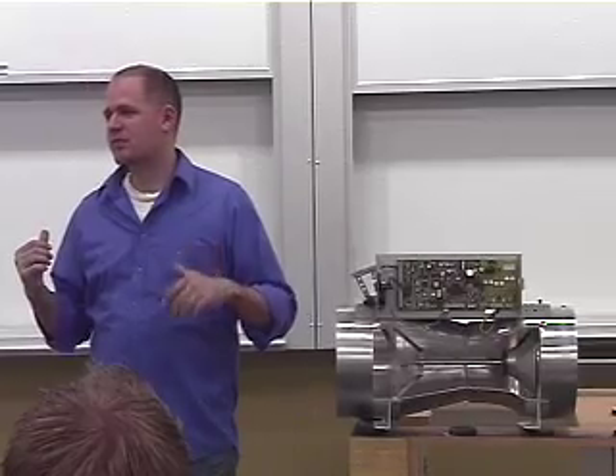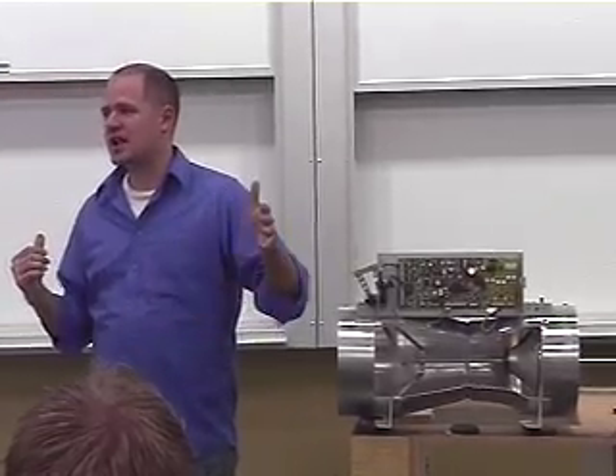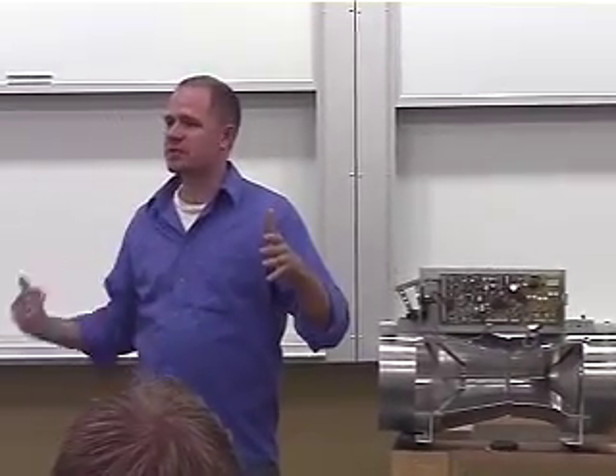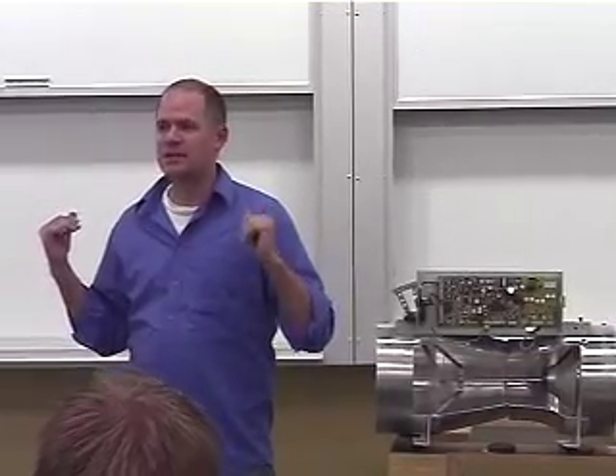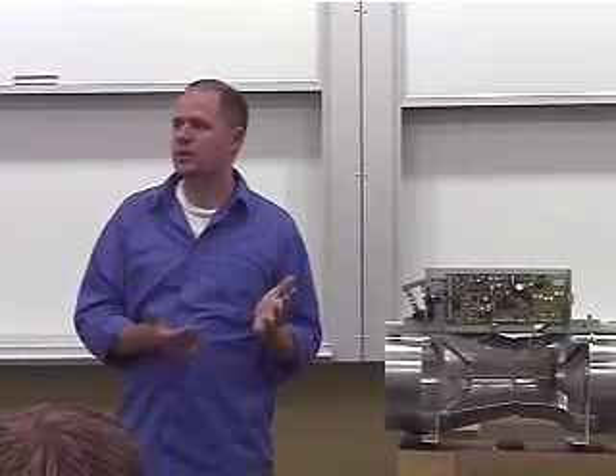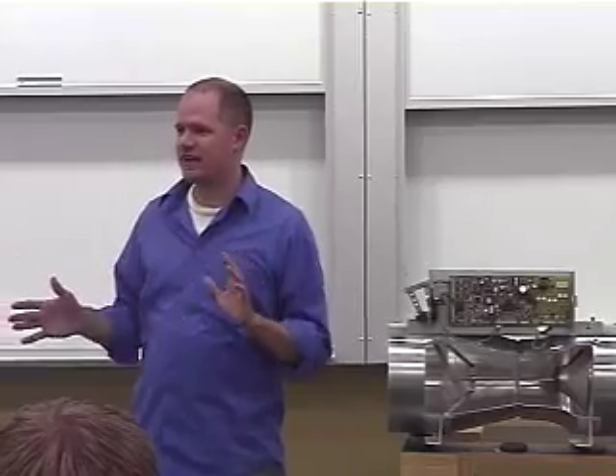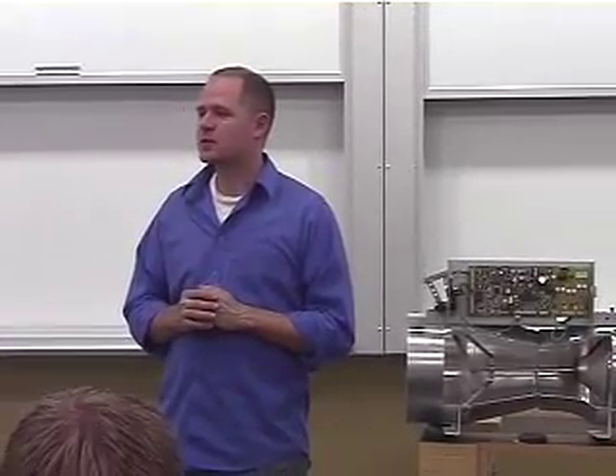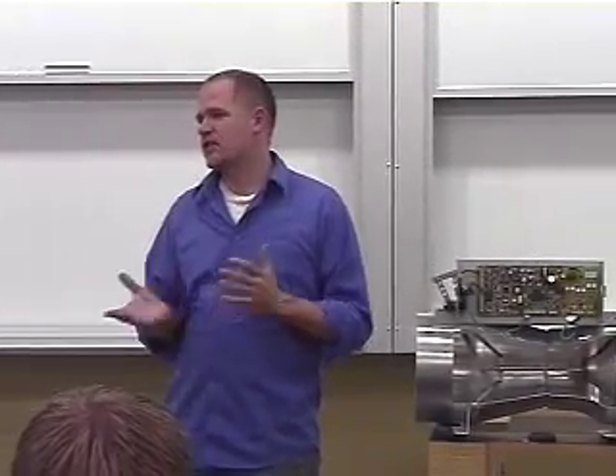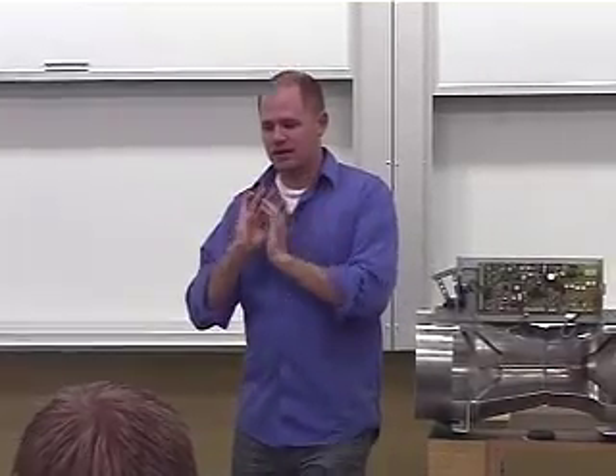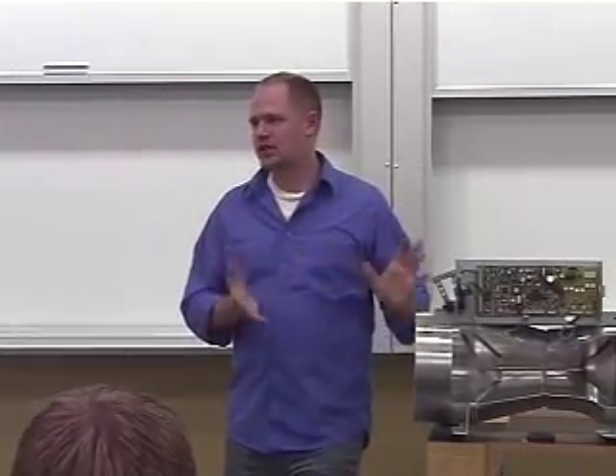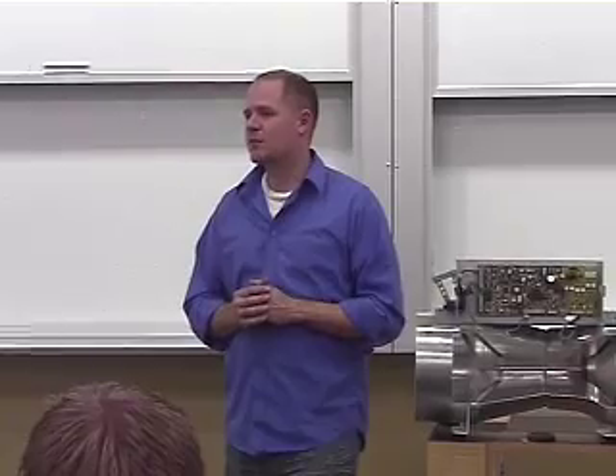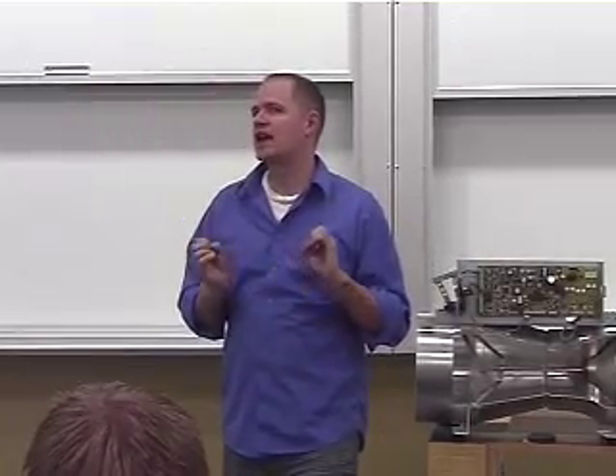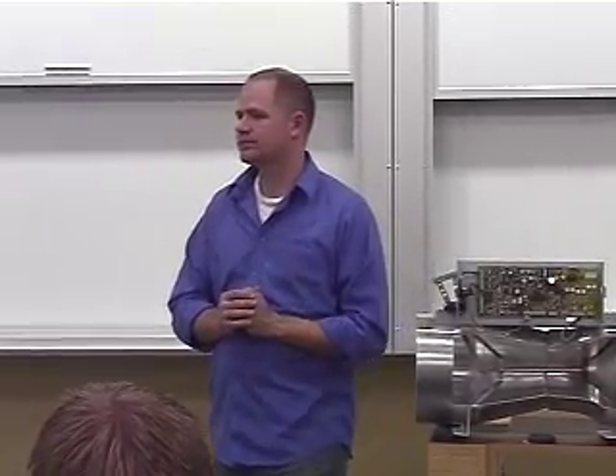So your jets typically will also fail open to get exhaust out of the room in case somebody closes down the fume hoods and your supply fails open. But that depends on the drawings, what the engineer asked for. There's a lot of variables, so it's not a hard, fast rule. But that's how those work. And so fire code is taken care of by the fans. We just put them in the safest position we can for making assumptions of not knowing what's going on in the building.